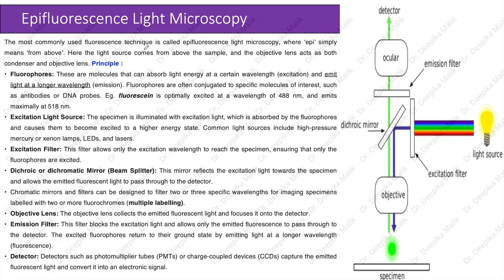Now let us see the principle and working of epifluorescence light microscopy. The most commonly used fluorescence technique is called epifluorescence light microscopy, where 'epi' simply means 'from above.' Here the light source comes from above the sample, and the objective lens acts as both condenser and objective lens.